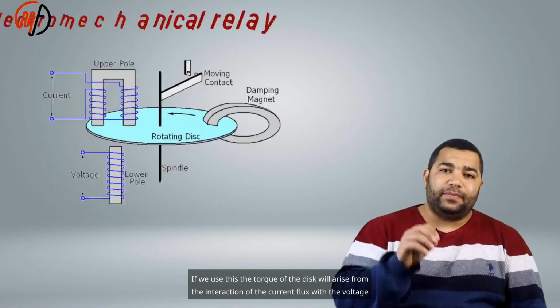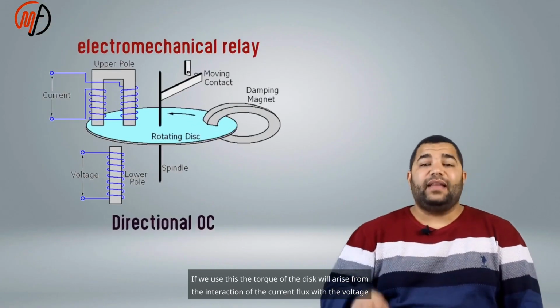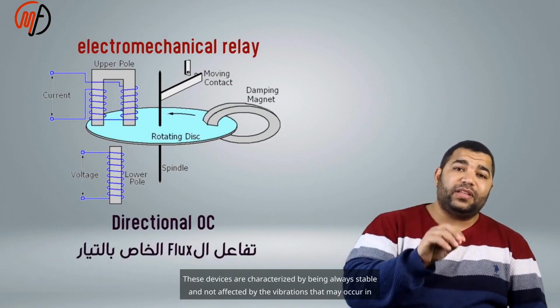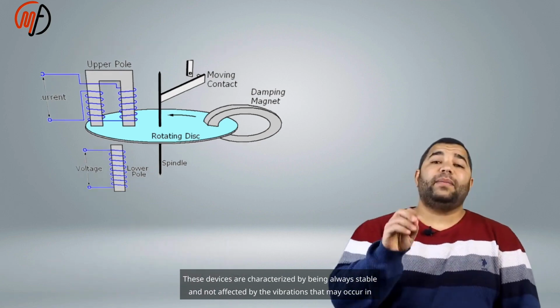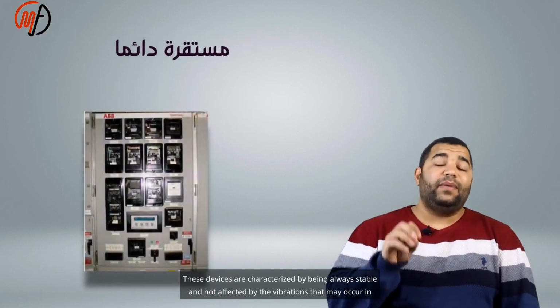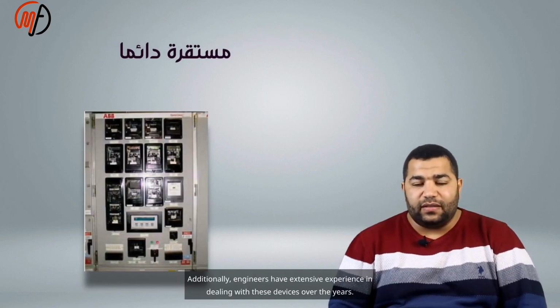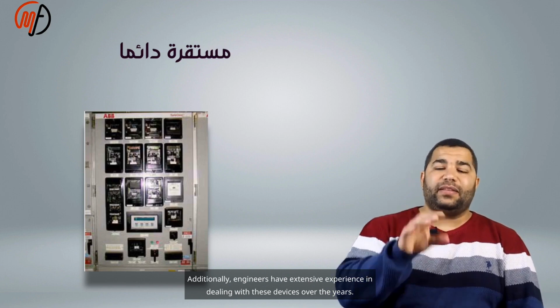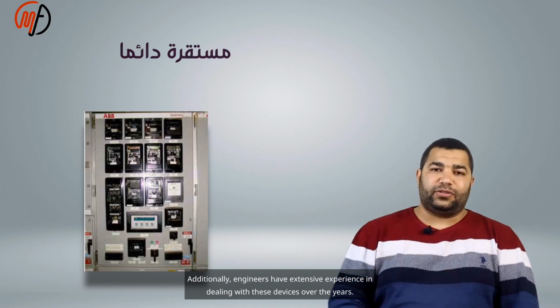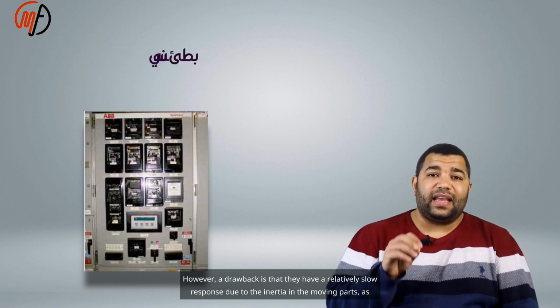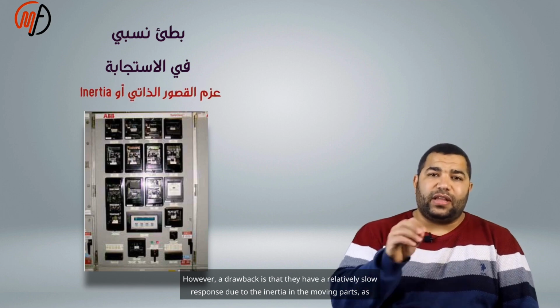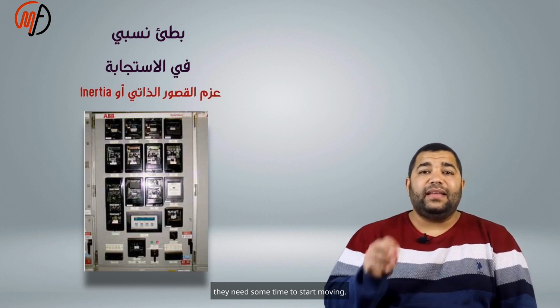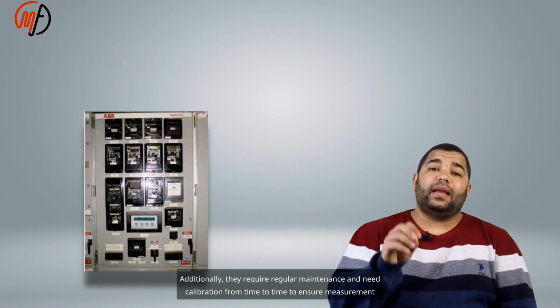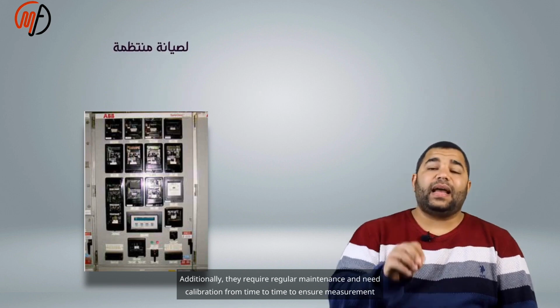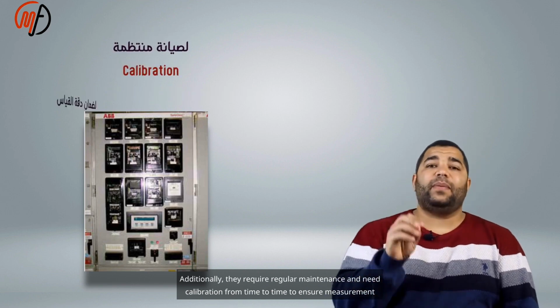If we use this, the torque of the disk will arise from the interaction of the current flux with the voltage flux. These devices are characterized by being always stable and not affected by the vibrations that may occur in the electrical network. Additionally, engineers have extensive experience in dealing with these devices over the years. However, a drawback is that they have a relatively slow response due to the inertia in the moving parts, as they need some time to start moving. Additionally, they require regular maintenance and need calibration from time to time to ensure measurement accuracy. This relay is a high burden for the CT and VT.